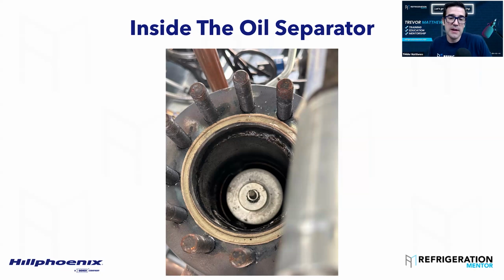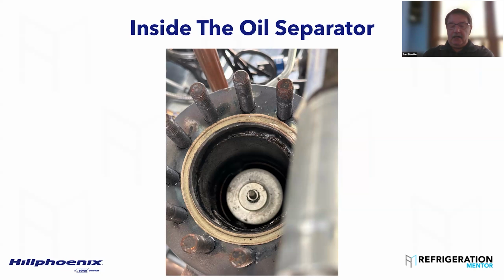but try to be better the next time. And so some of the things you will see is a high pressure differential across the oil separator would be one thing. Yeah, you want to be careful. You want to look at it. Anything continuous 12 psi differential or greater. And what I mean by continuous is not momentary, because you can have a 25 psi differential momentarily when something comes out of defrost and another compressor comes on. So a continuous differential of 12 psi, you'll want to change that filter.